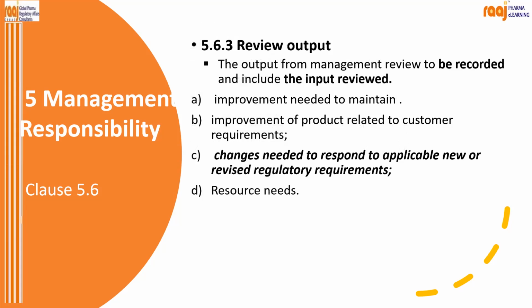Then what will be the review output? The output from the management review is to be recorded and includes the input reviewed, improvement needed to maintain the effectiveness, improvement of product related to customer requirement, changes needed to respond to applicable new or revised regulatory requirements, and resources needed. These are the outputs.